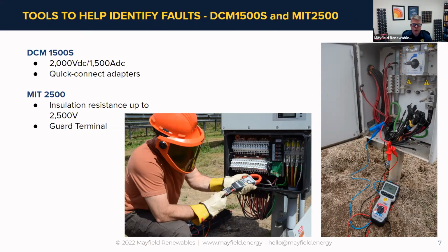Well, there was a question that came up before this webinar even started, around whether insulation resistance testing is destructive. Beryl, I've seen that you're on the call, so if you want to clarify the question, please do. I was understanding it to be about the cable system itself, doing multiple IR tests, maybe once a year or every 6 months, depending on your protocol, putting this high voltage on the conductors. So I guess that's the big question: is this a destructive test over time?